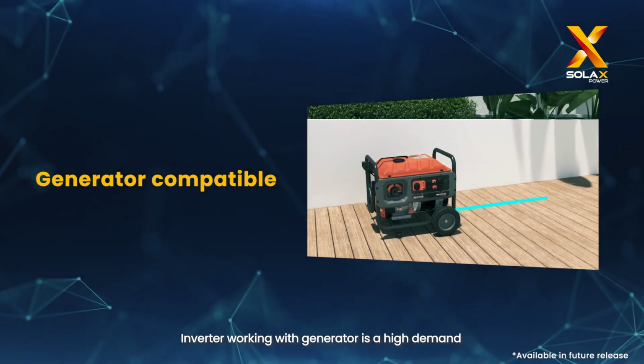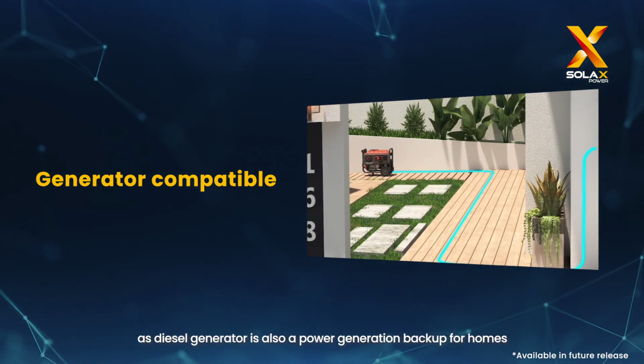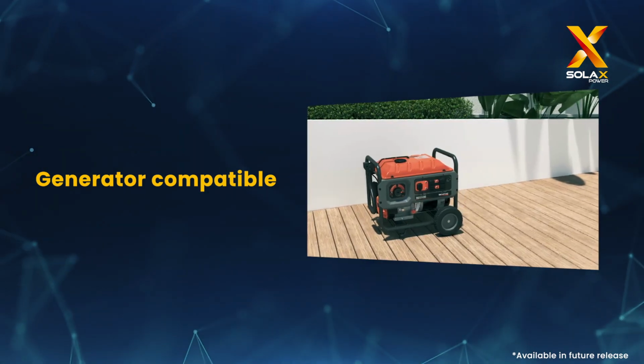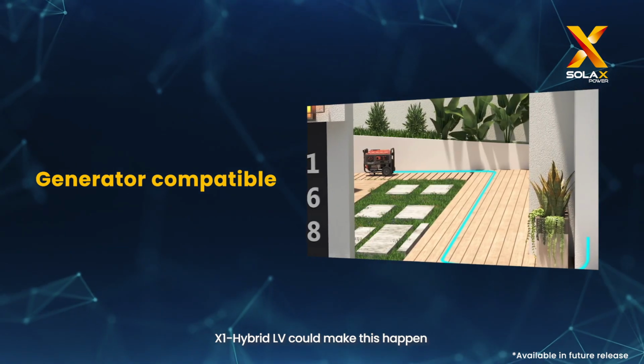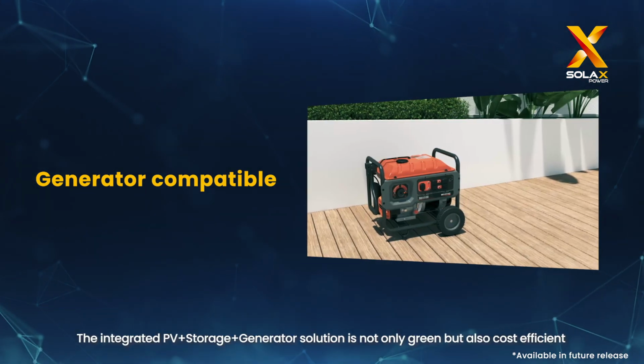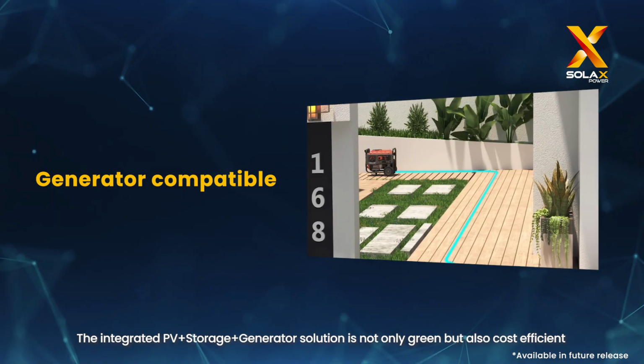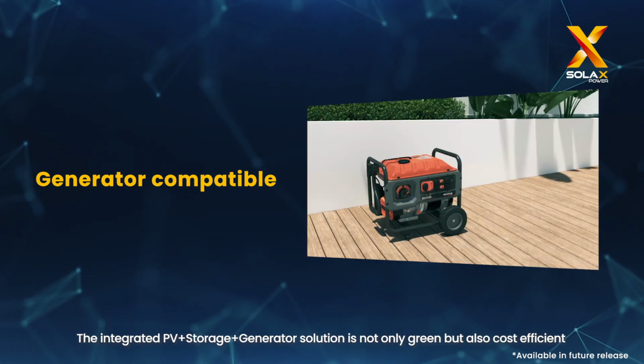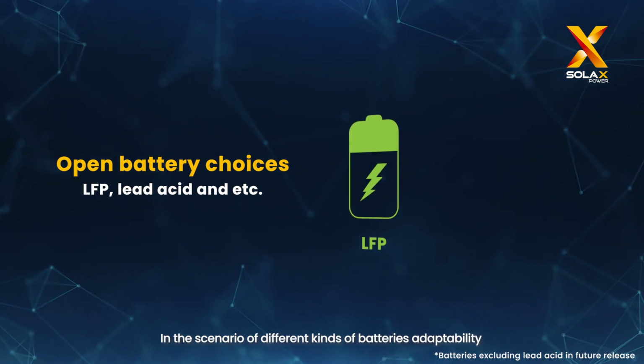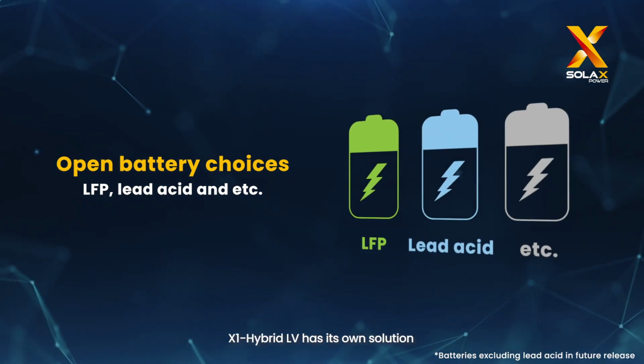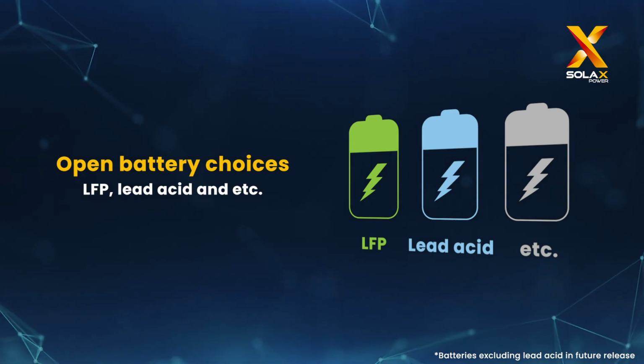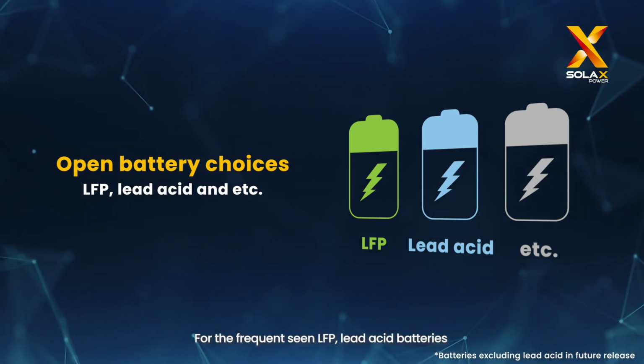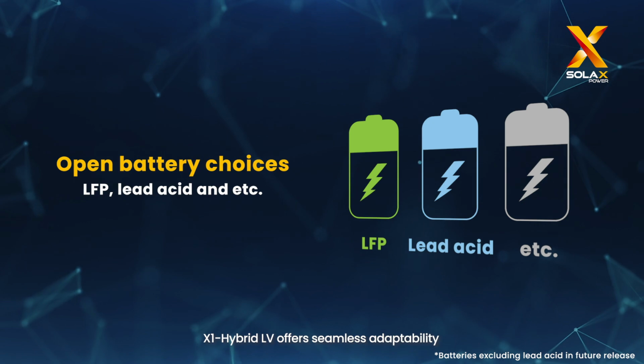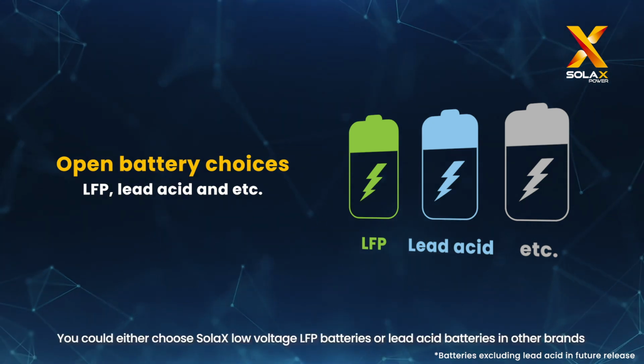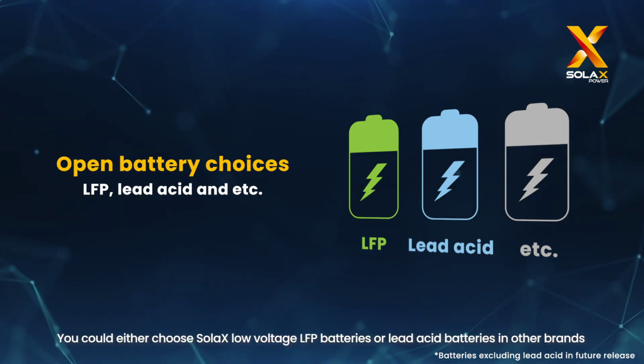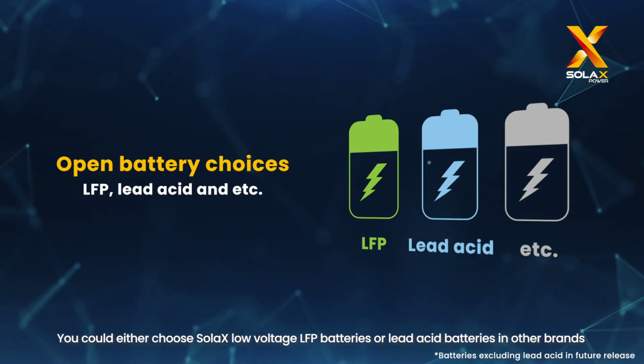Inverter working with generator is a high demand as diesel generator is also a power generation backup for homes. X1-Hybrid LV could make this happen. The integrated PV plus storage plus generator solution is not only green but also cost efficient. In the scenario of different kinds of batteries adaptability, X1-Hybrid LV has its own solution. For the frequent seen LFP, lead acid batteries, X1-Hybrid LV offers seamless adaptability. You could either choose SolaX low voltage LFP batteries or lead acid batteries in other brands.